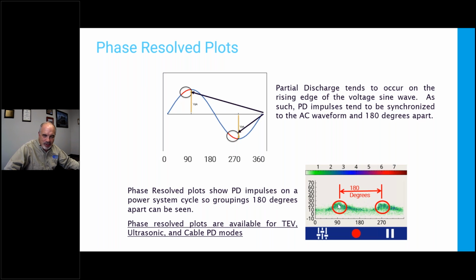If you had a vertical line that said it was always occurring at exactly the same phase angle, PD doesn't occur at exactly the same voltage, so it doesn't occur at exactly the same phase angle. That would tell me I'm looking at something electronic. If I see six vertical lines, I'd say I'm looking at an inverter or some sort of three-phase drive. Those sort of things are going to help me determine what I'm listening to. Because we really are listening to ultrasonic energy or picking up TEV. Those are not direct measurements. We're inferring from those measurements that PD exists. So that's the value in the phase resolve plot.